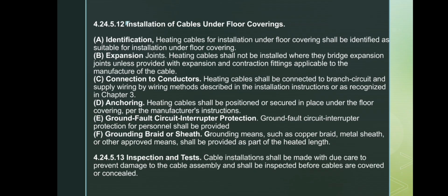Next is the installation of cable under the floor coverings. For heating cables installed under floor coverings, the cable must be specifically identified as suitable for this type of installation. Cables cannot cross expansion joints unless special expansion fittings are provided. Connections to supply conductors must follow the installation instructions or other approved wiring method in Chapter 3. The cables must be properly secured under the flooring as the manufacturer directs, and GFCI protection is required for safety.